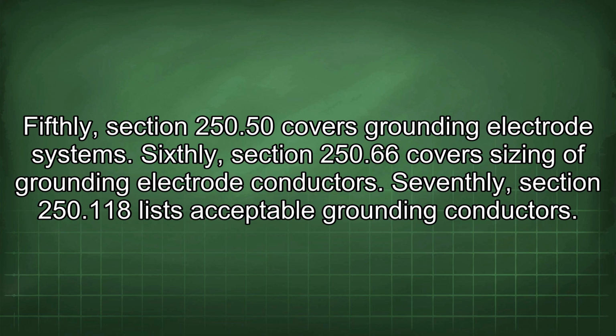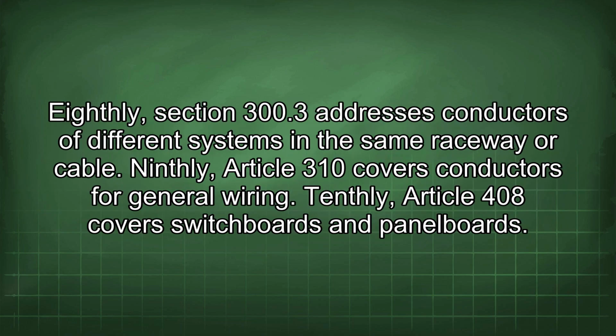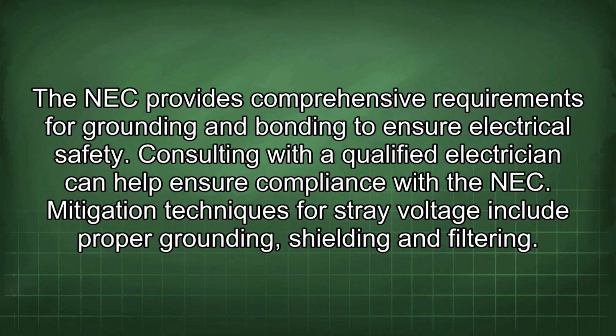Seventhly, Section 250.118 lists acceptable grounding conductors. Eighthly, Section 300.3 addresses conductors of different systems in the same raceway or cable. Ninthly, Article 310 covers conductors for general wiring. Tenthly, Article 408 covers switchboards and panel boards. The NEC provides comprehensive requirements for grounding and bonding to ensure electrical safety. Consulting with a qualified electrician can help ensure compliance with the NEC.